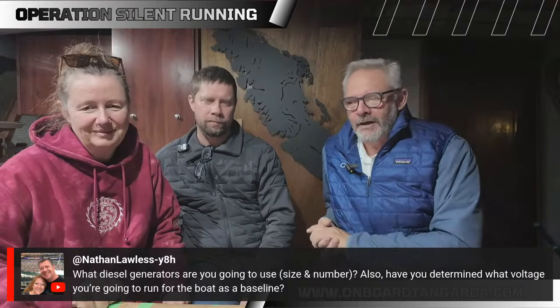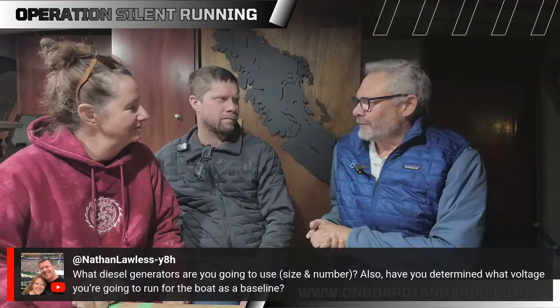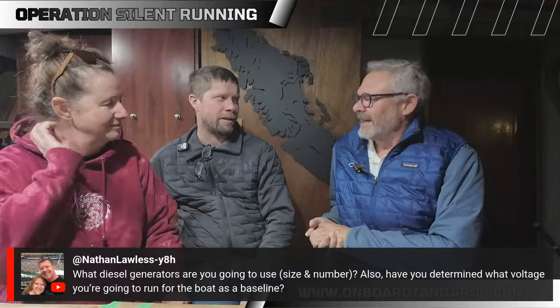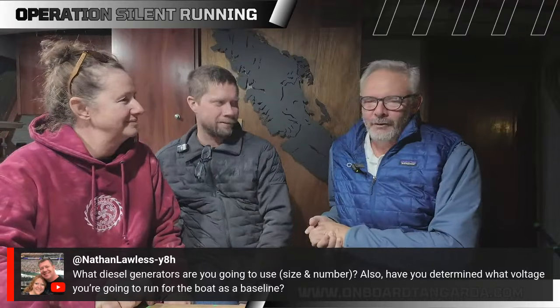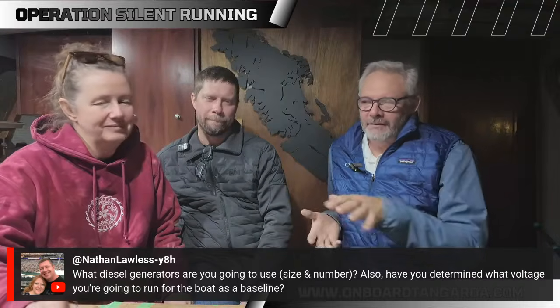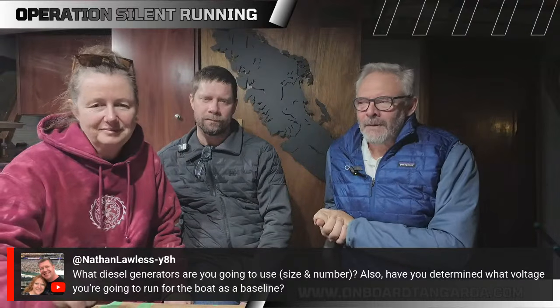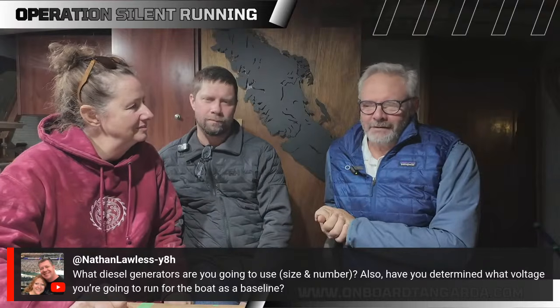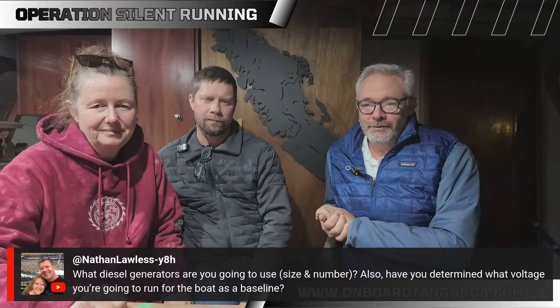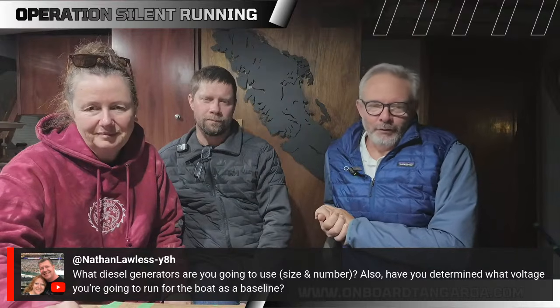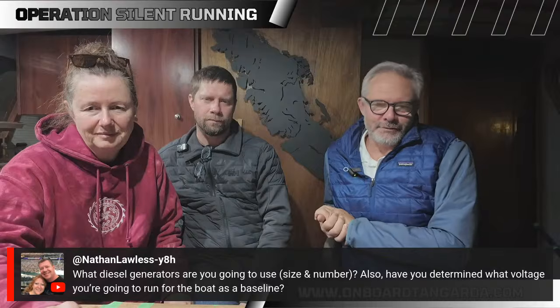In the retail market, we found people promising best case performance around 230, maybe 238, though some were more like 248. So if that's the case, even with some offering a bit better, frankly you're not looking at massive improvements in generator performance. What you're doing is just using less of them, so your fuel burn is going to be a little less than something producing 200 horsepower or so, and you'll be more efficient. Your emissions will be better too, because a constant speed, constant power generator reduces your actual environmental impact by about 60% compared to something only running at 50% efficiency.